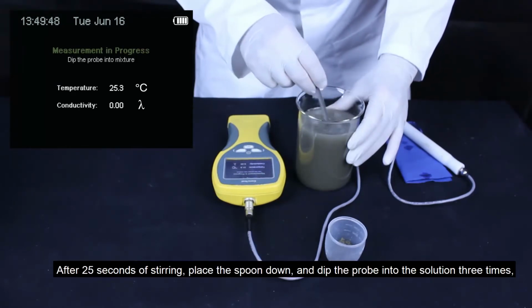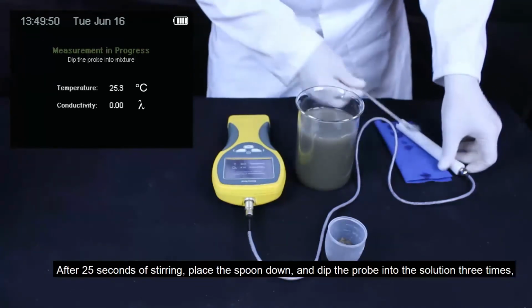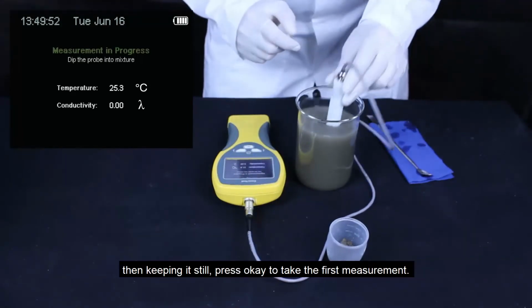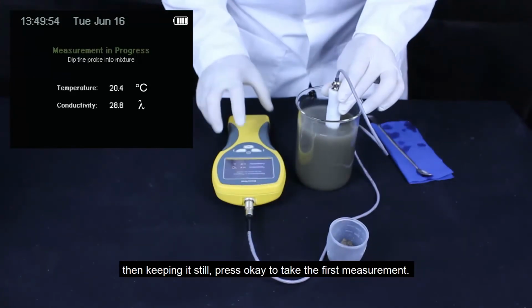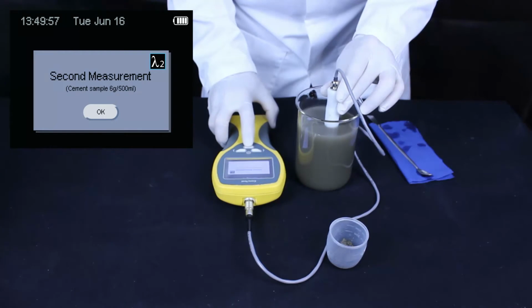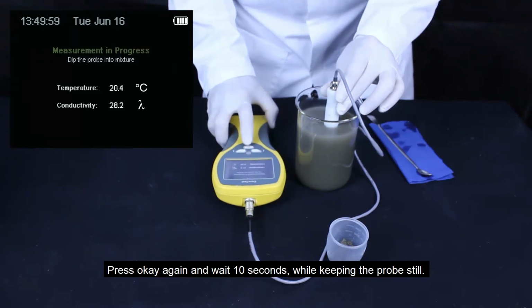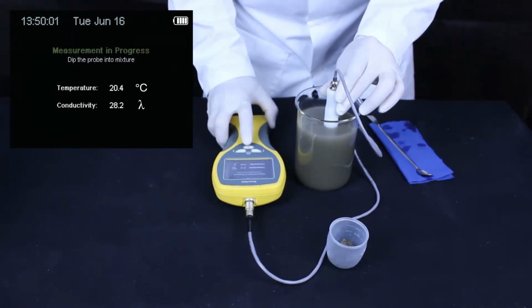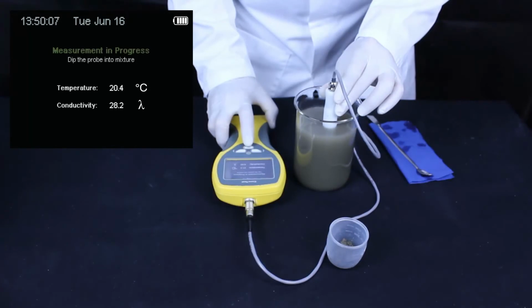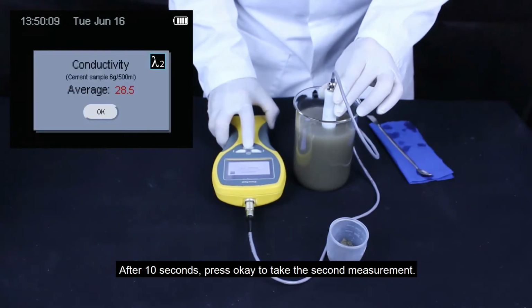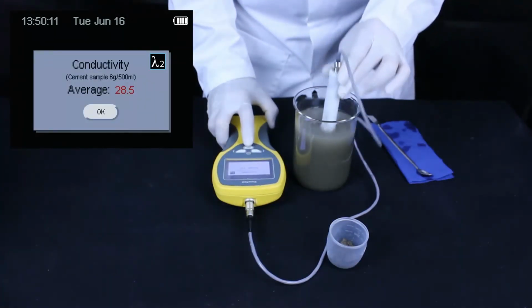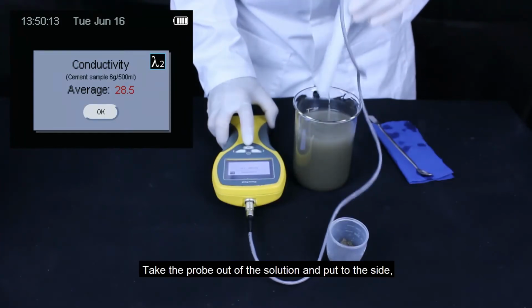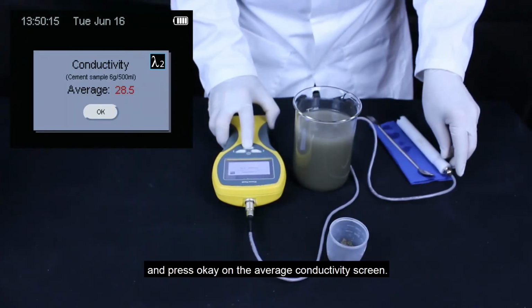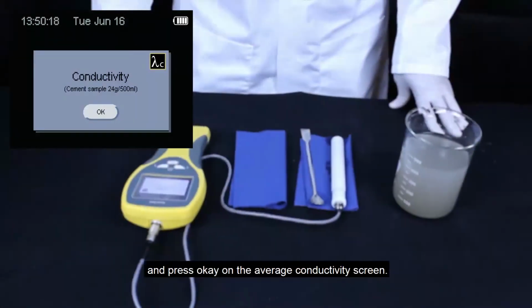After 25 seconds of stirring, place the spoon down and dip the probe into the solution 3 times, then keeping it still, press OK to take the first measurement. Press OK again and wait 10 seconds while keeping the probe still. After 10 seconds, press OK to take the second measurement. Take the probe out of the solution and put to the side, and press OK on the average conductivity screen.